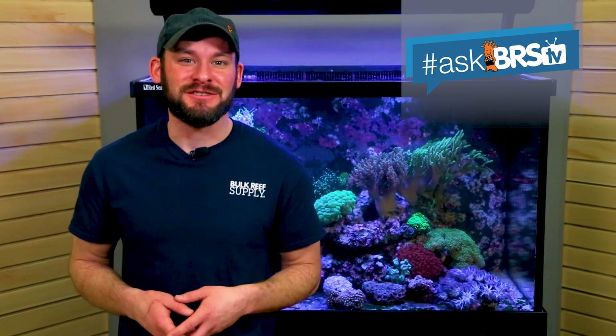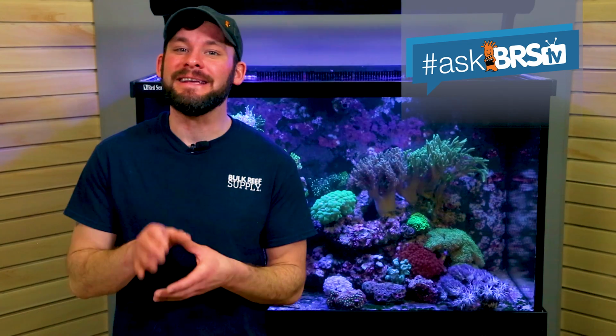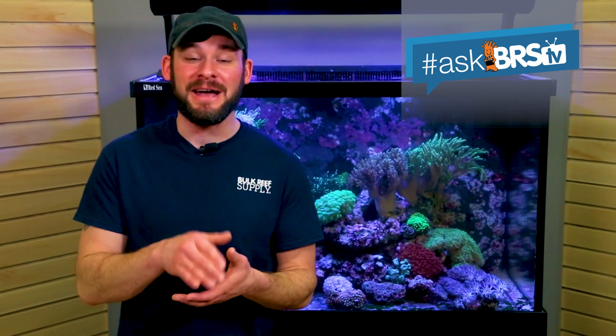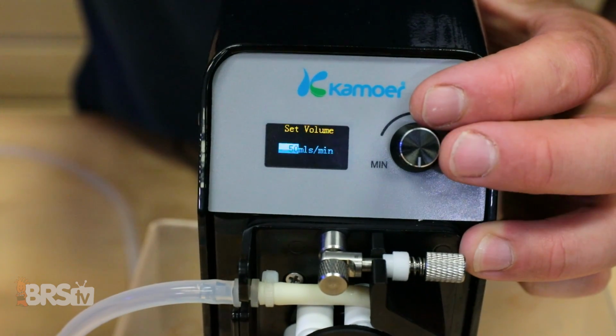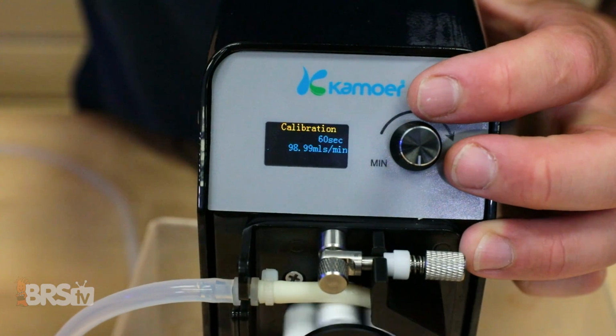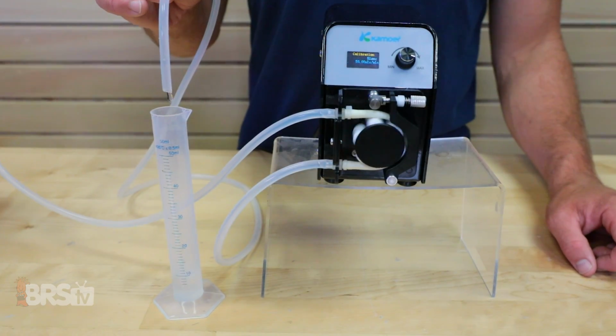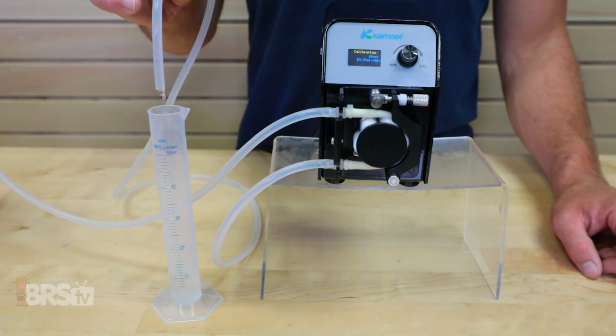After replacing the dosing tubing, it's definitely best practice to recalibrate the pump before putting it back to use, and I'd actually recommend rechecking the calibration again after a few days of use with the new tubing, after it's had time to conform to the pump head.